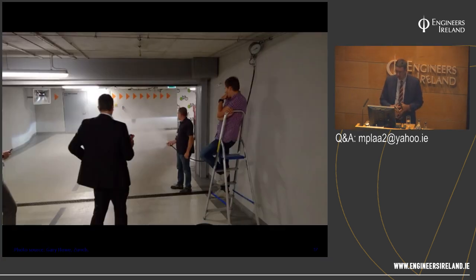Here's an example of a test of an underground car park, multiple levels of underground car park. The customer had a nice shiny certificate to say that the system had been signed off by the installer. My question was, on a dry system, how long did it take you to get water from the valve set to the hydraulically most remote point of the installation? And the answer was, we haven't tested it.